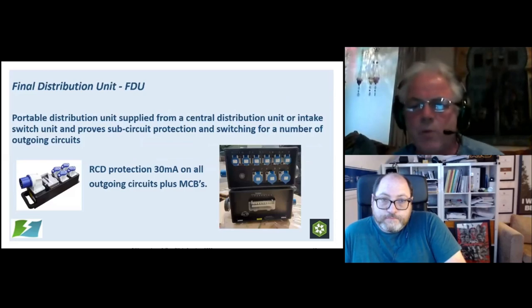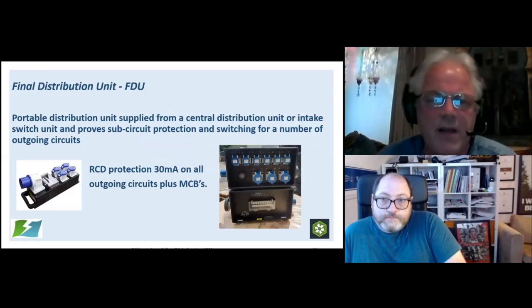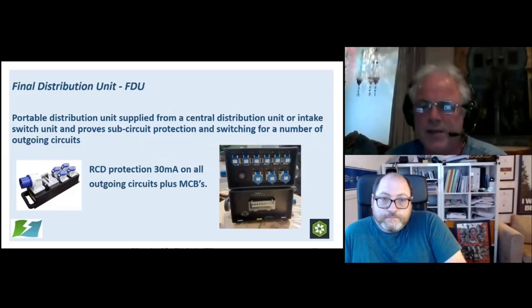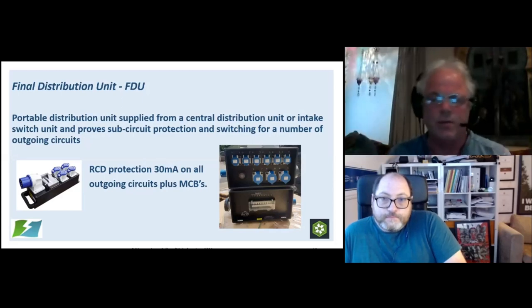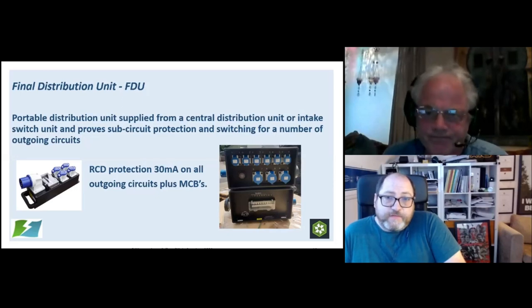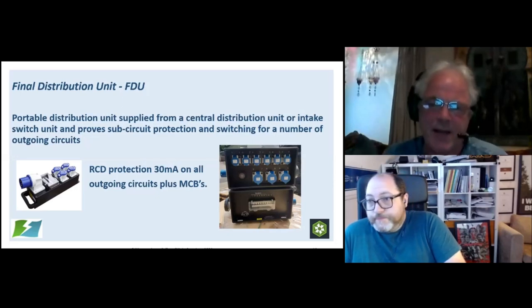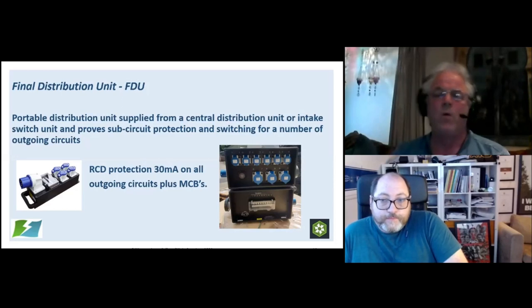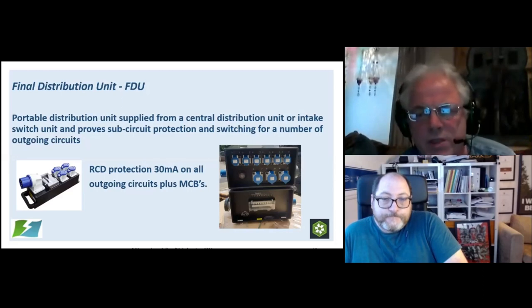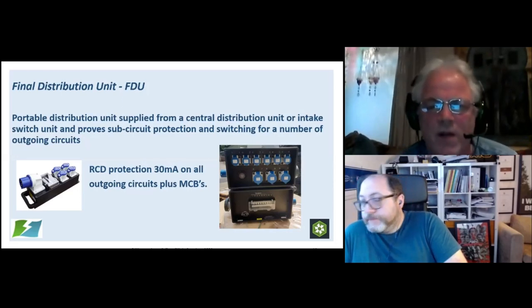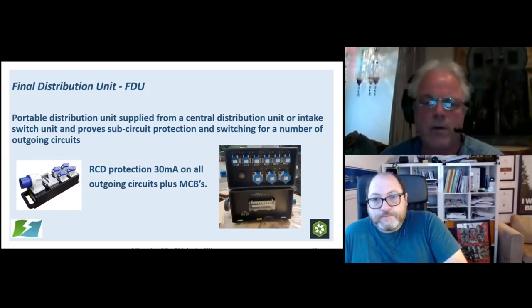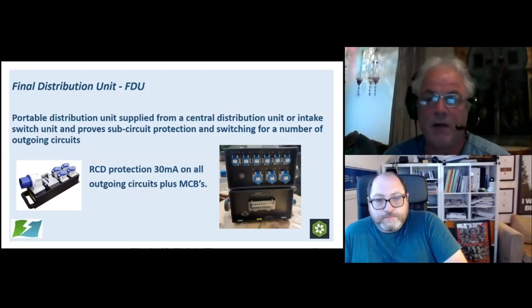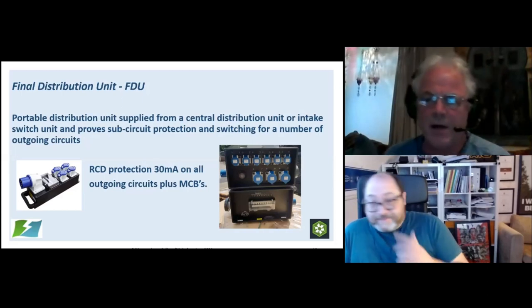Your final distribution units will be nearer to the load, right by the load hopefully, or very close to it, and we get the supply to them, and then these will feed out to your final circuits, to your pieces of equipment, your lights, your heaters, your air conditioning, all sorts of things. And these are the ones we want to be resetting during an event. Yeah, these will be the instantaneous 30 milliamp RCDs. These should be the ones that operate should there be a piece of equipment that has a fault on it, or develops a fault, or gets damaged during use. And it's the pieces of equipment that most of the time cause issues and get damaged, and they're the ones that really will quite often go to fault. So it's the final distribution unit RCDs, hopefully, that will operate rather than taking out the whole supply.